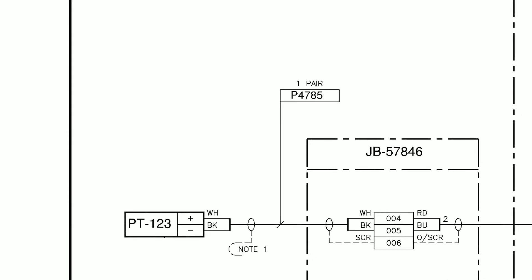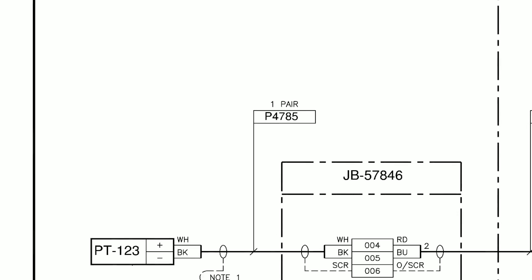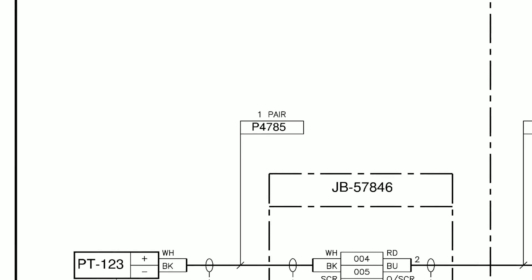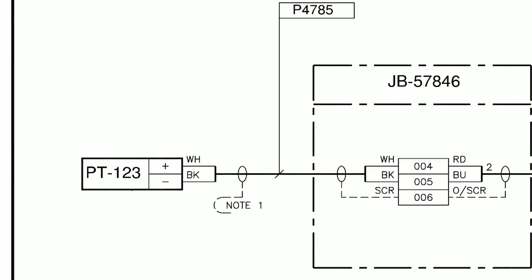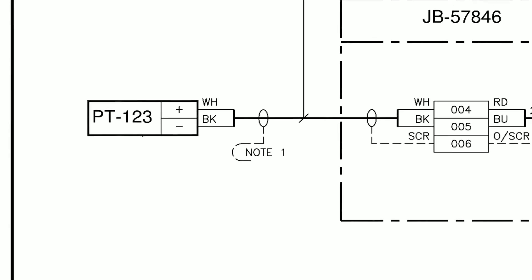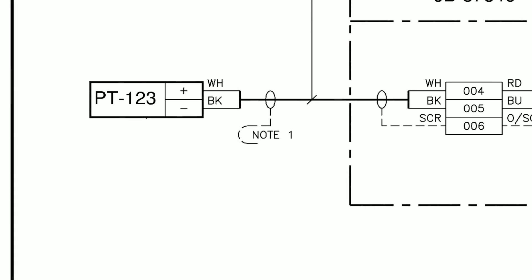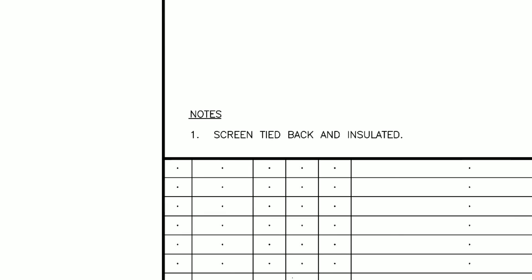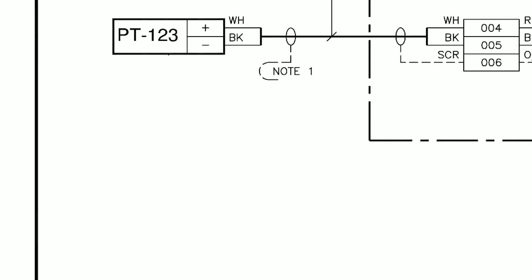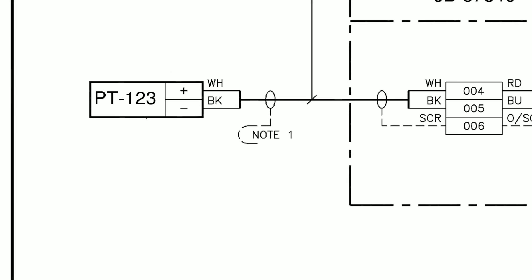We can see it is connected via a one-pair cable, which is P4785, the cores of which are black and white. We can also see there is a note labelled as note 1. Looking down at the notes key in the bottom left, we can see it states that the screen of the cable is tied back and insulated. Now this is done to prevent ground loops, but that's something we'll talk about in a future video.